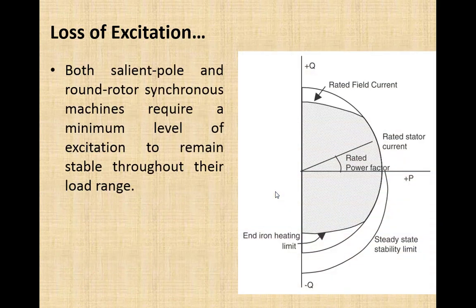So here I will explain this concept, what happens due to loss of excitation, with the help of this loading capability diagram of the synchronous generator. This loading capability diagram is developed on the power plane, where the horizontal axis is the real power and the vertical axis is the reactive power. Negative real power means consumption, positive real power means generation.